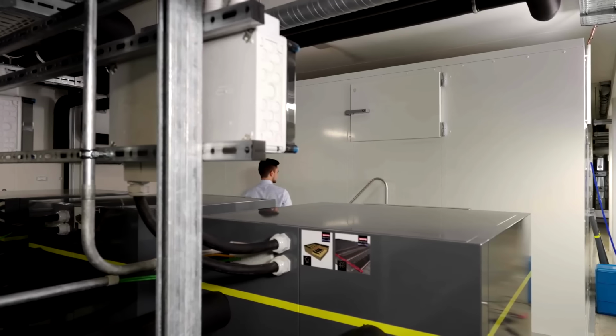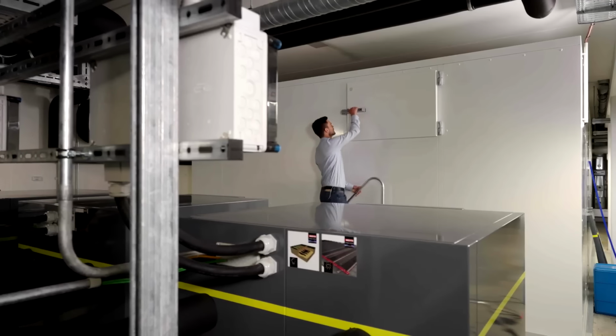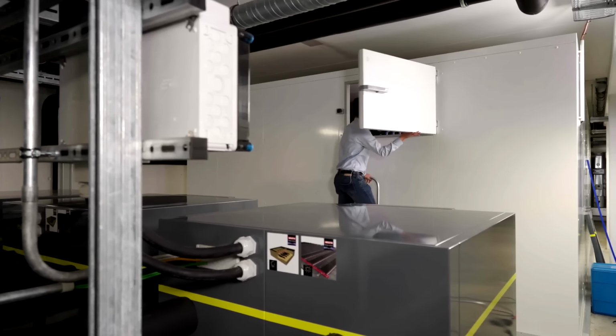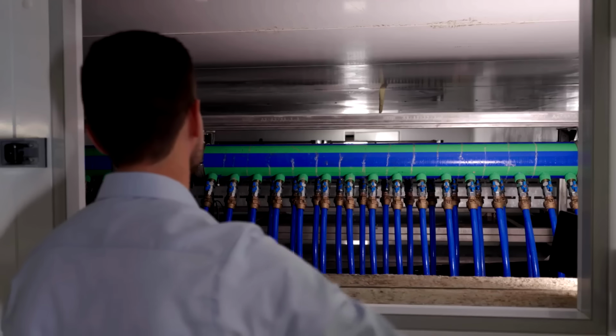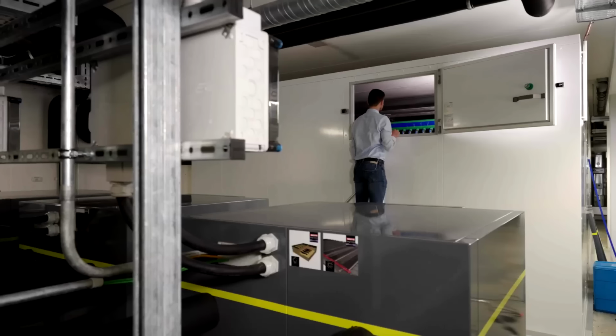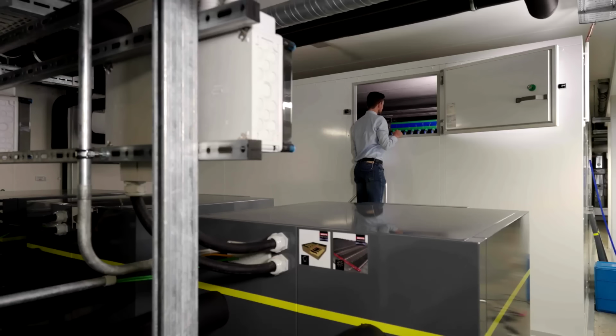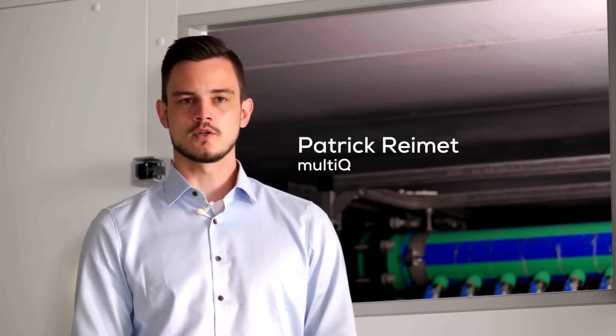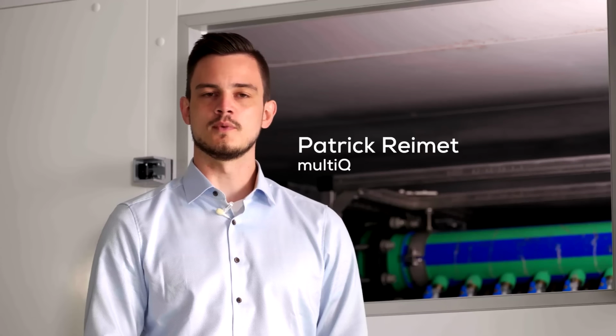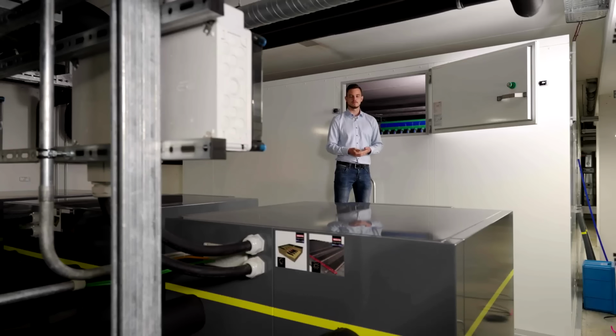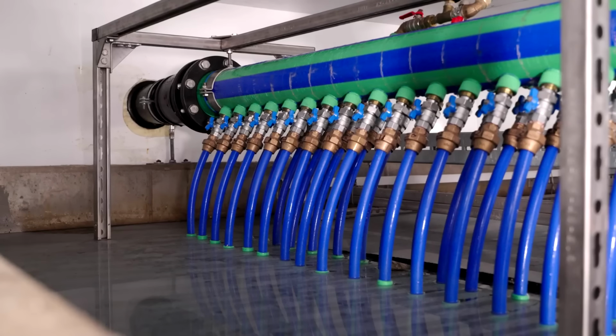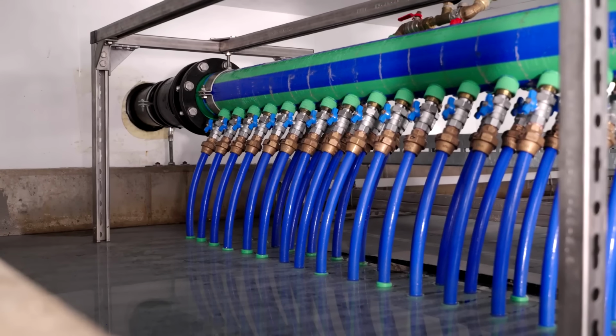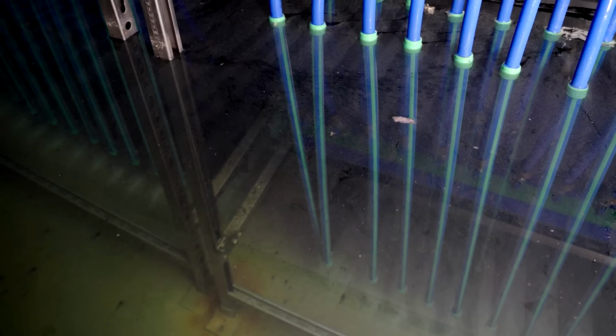The company generates not only heat, but also cooling capacity, which is stored in this large water tank. It holds 60,000 liters and is located right next to the heat pumps. The heat pumps generate heat for the building, and in the process, cool air is automatically produced. We can use this to cool the building or the equipment in the server rooms. This means that the cold air produced by the heat pumps also flows to the 60 heat exchangers in the tank. As a result, the water cools down.